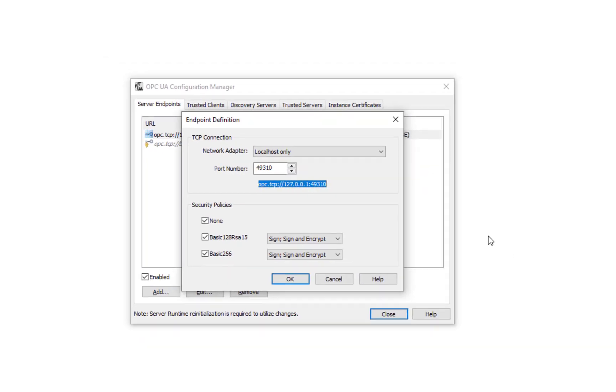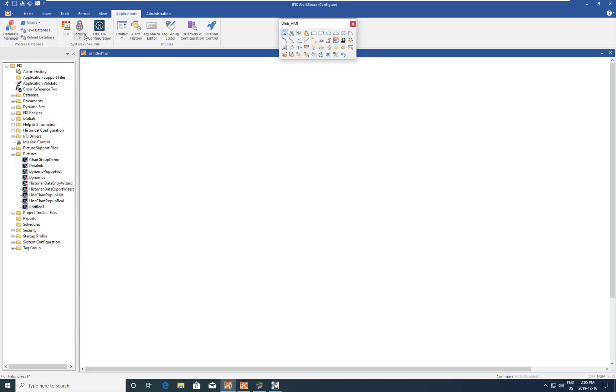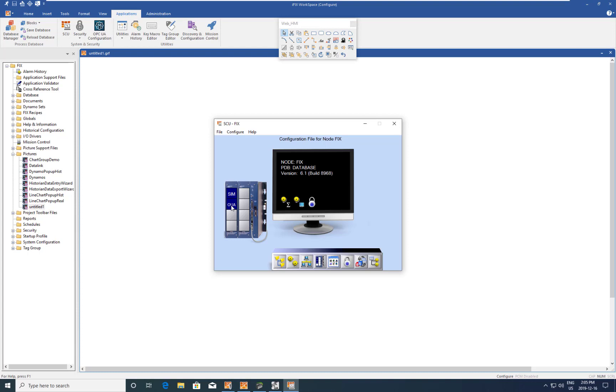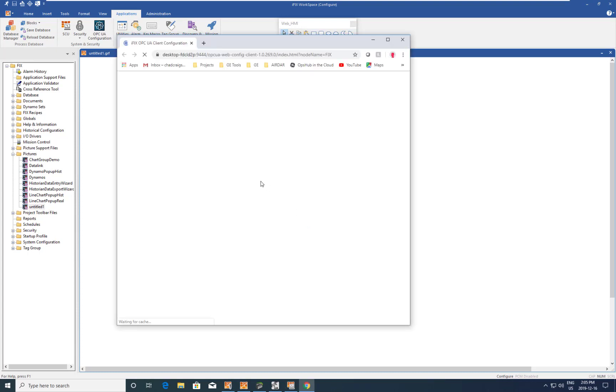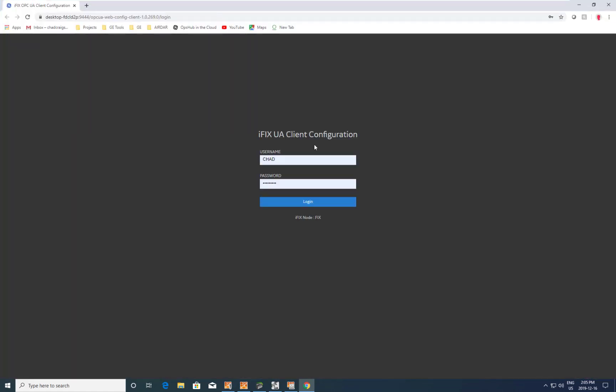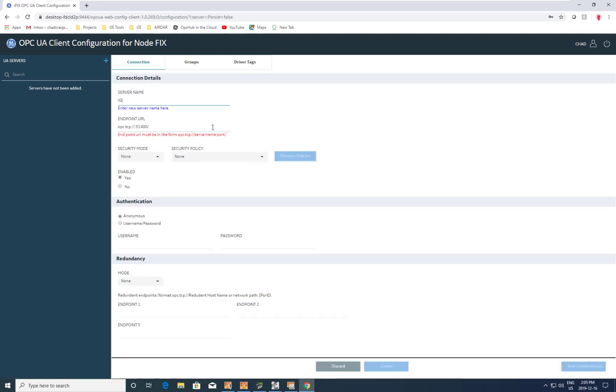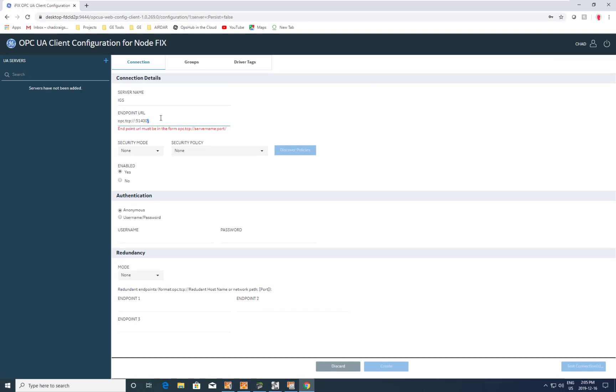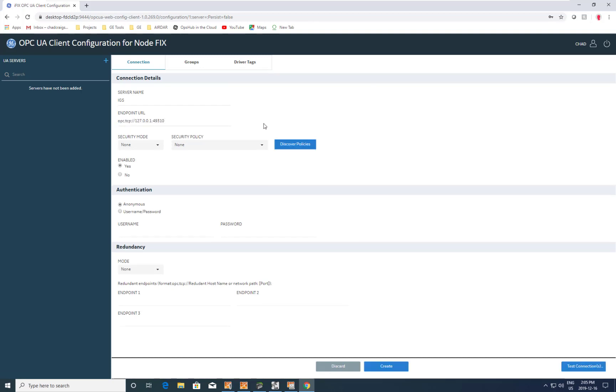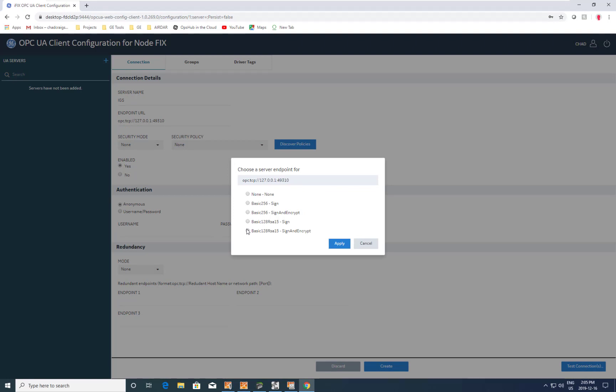We're going to copy that endpoint and open up the iFix OPC UA client, which is a driver. It opens up a web-based configuration which takes us to a login page. We log in and we can see that right now we haven't added any servers, so we're going to add the IGS as an OPC UA server. We'll put in that URL, discover which policies it supports, and for this demo we're going to show setting up with the most secure endpoint that the IGS currently supports.